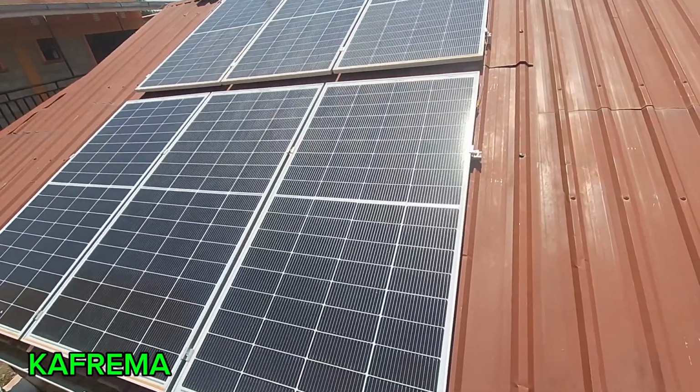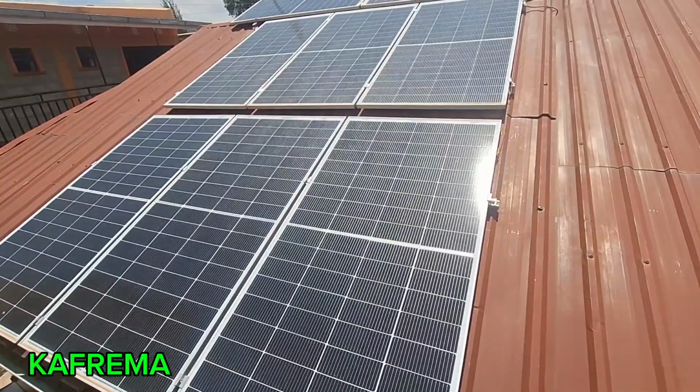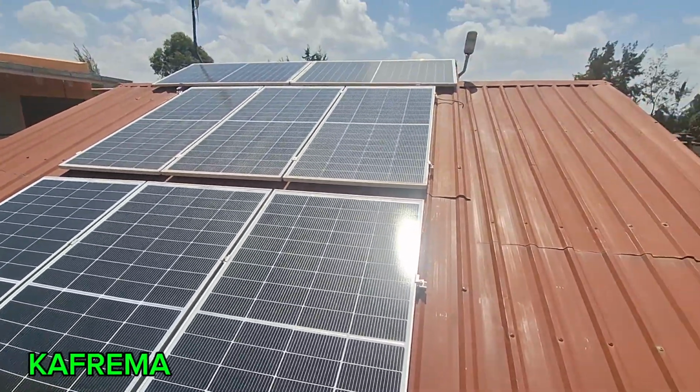Each panel has also its current. If you connect the panels in series, you add the voltage, but the current will be the same. Get this right. If you connect in series, you add the voltage. That's why we said the VOC is very important. You add the voltage.